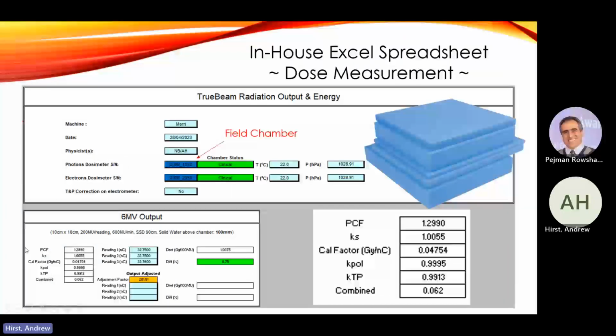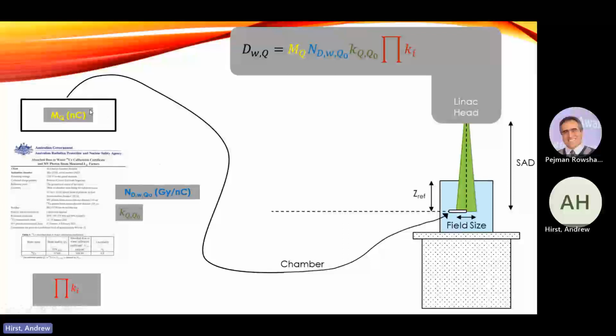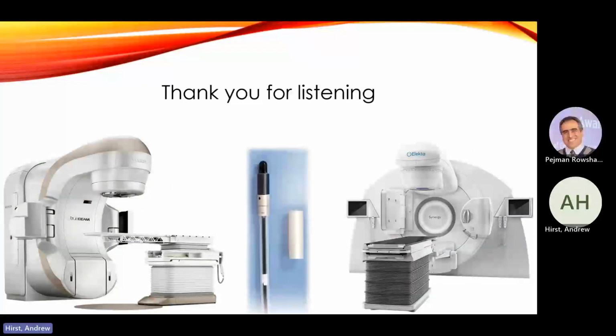So once we have all our factors from the certificate, all our measurements, we take a reading in nanocoulombs from our electrometer, times by all of those coefficients and correction factors, and we end up getting our dose. And I want to stress, that's a dose for that point, for these conditions. You change anything else and it will change. You change your field size, your SSD, all of those things will change the dose. So we relate everything to that one point and one set of conditions through a set of other factors. So yeah, that's everything I have.